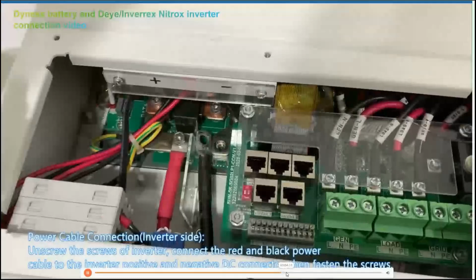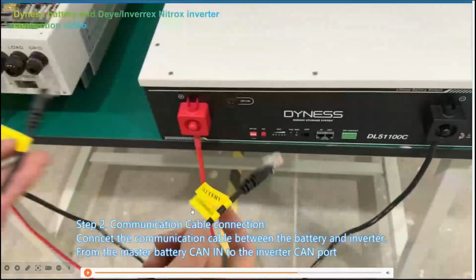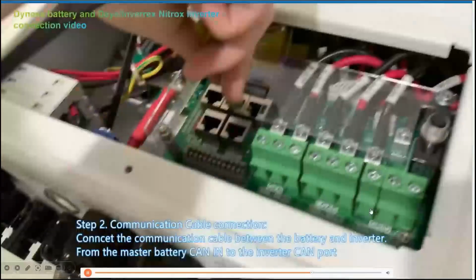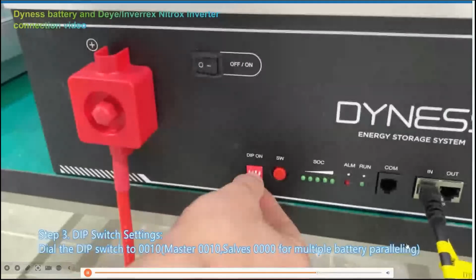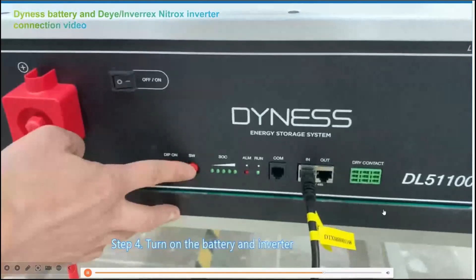And the positive cable. Let's move on. And then we need to distinguish which is to the battery side and which is to the inverter side. Connect to the battery CAN input, and to the inverter, the BMS port. And then set the dip switch to the master setting, because here there is only one battery.